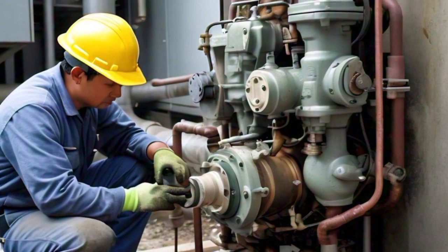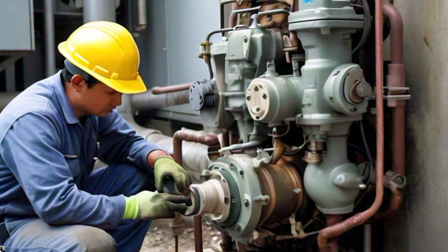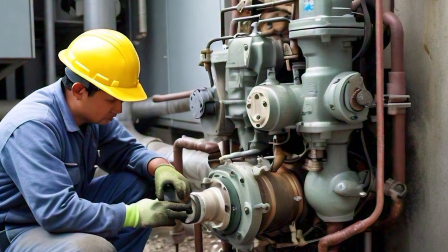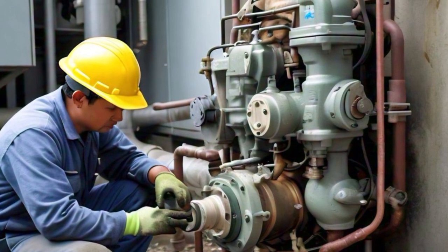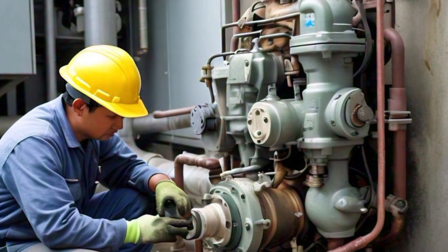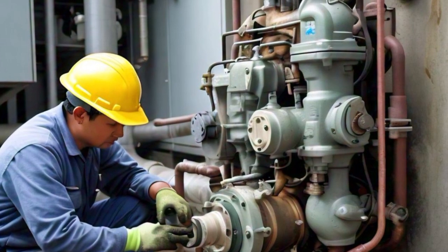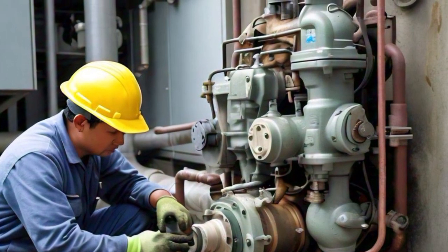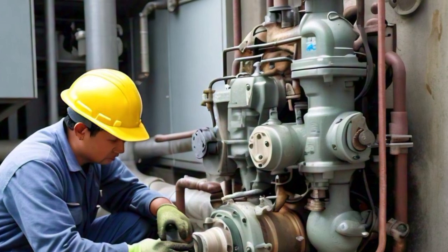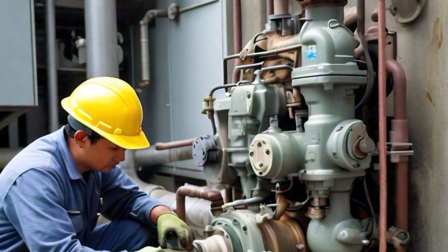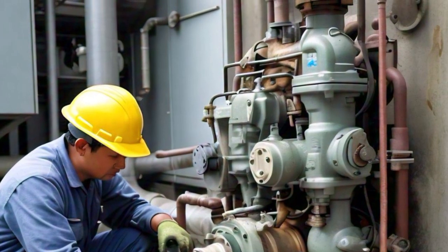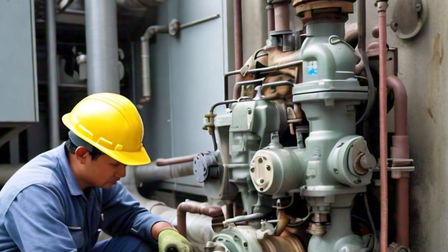Number 3. A decrease in the diameter of the supply line. Your pump is made to work with input lines of a specific diameter. We have observed instances where individuals have used reduction couplings to attach a hose or line that is smaller than what is advised. Additionally, depending on the type of intake line you employ, the line may crimp or become sucked in on itself.